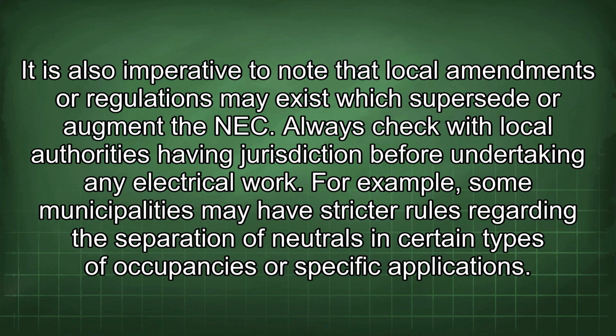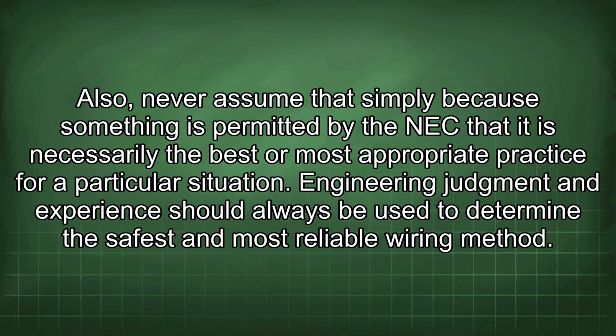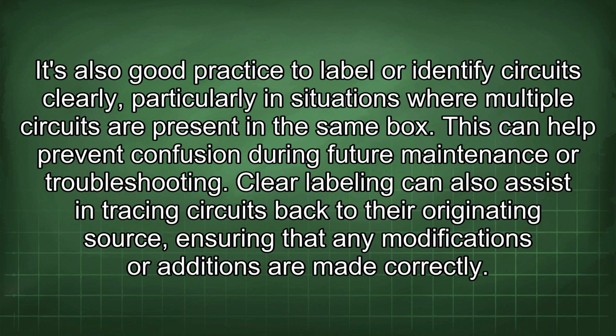It is also imperative to note that local amendments or regulations may exist which supersede or augment the NEC. Always check with local authorities having jurisdiction before undertaking any electrical work. For example, some municipalities may have stricter rules regarding the separation of neutrals in certain types of occupancies or specific applications. Also, never assume that simply because something is permitted by the NEC that it is necessarily the best or most appropriate practice for a particular situation. Engineering judgment and experience should always be used to determine the safest or most reliable wiring method. It's also good practice to label or identify circuits clearly, particularly in situations where multiple circuits are present in the same box. This can help prevent confusion during future maintenance or troubleshooting. Clear labeling can also assist in tracing circuits back to their originating source, ensuring that any modifications or additions are made correctly.